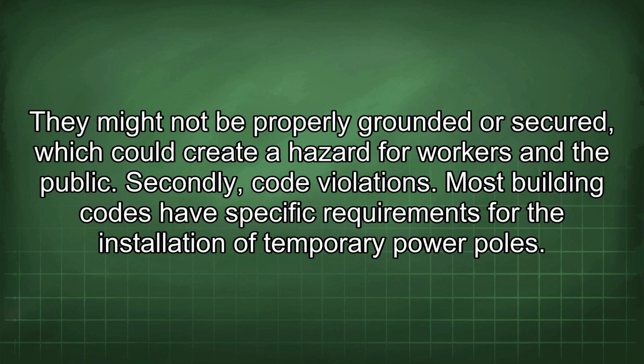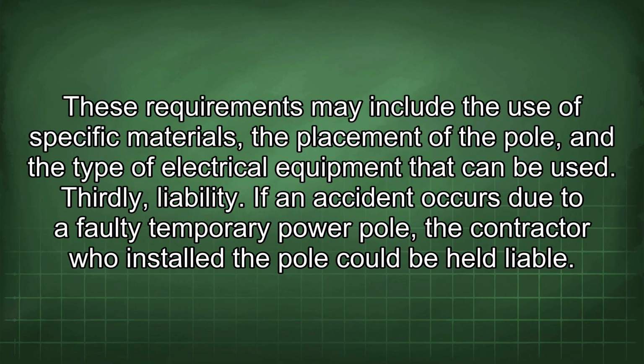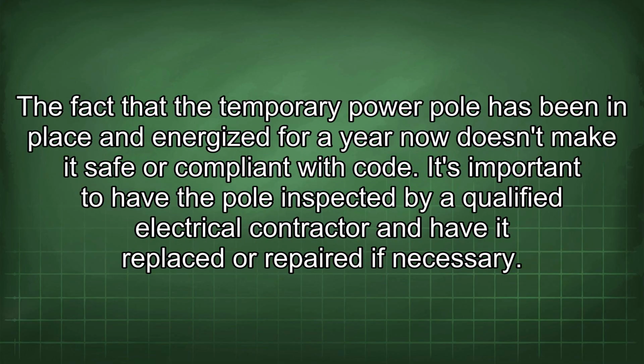Secondly, code violations. Most building codes have specific requirements for the installation of temporary power poles. These requirements may include the use of specific materials, the placement of the pole, and the type of electrical equipment that can be used. Thirdly, liability. If an accident occurs due to a faulty temporary power pole, the contractor who installed the pole could be held liable. The fact that the temporary power pole has been in place and energized for a year now doesn't make it safe or compliant with code.